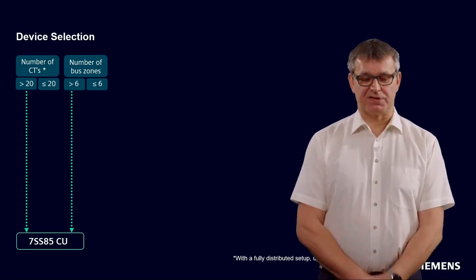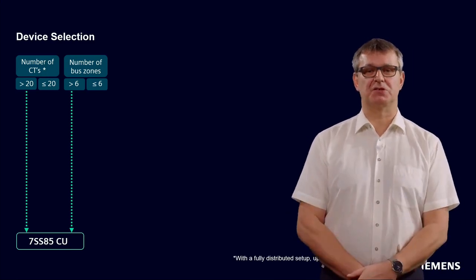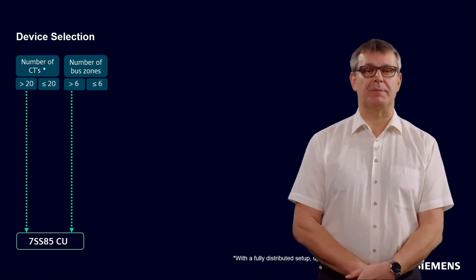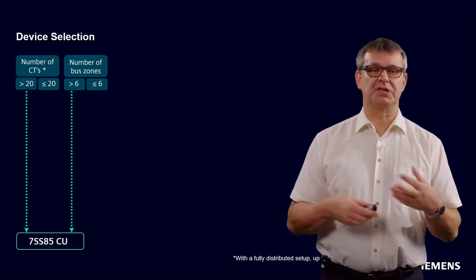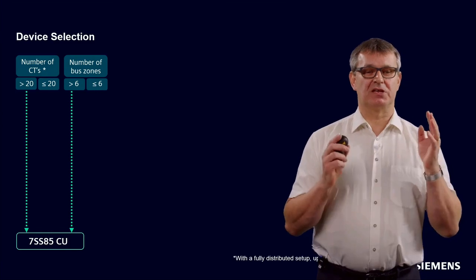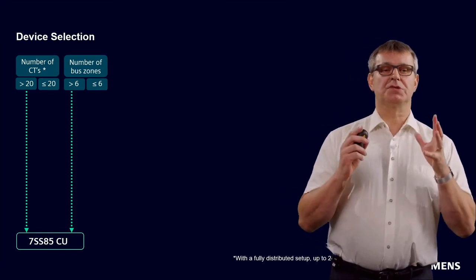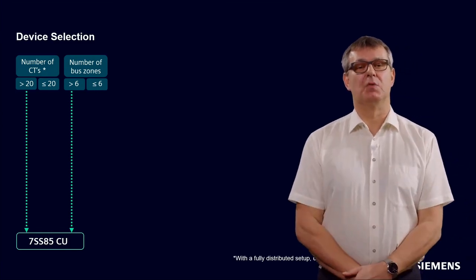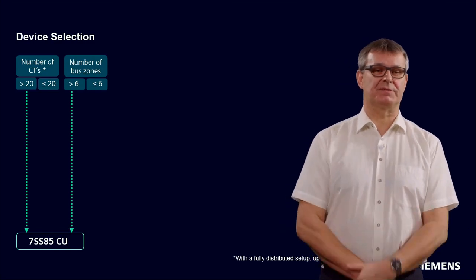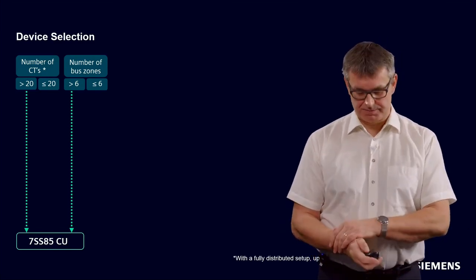Sometimes you may have the possibility to split the substation. If you have a sectionalization coupler, you can split it into 2 systems. But typically, in general, if you have more than 20 CTs and more than 6 busbar zones, please use the 7SS85 CU solution.